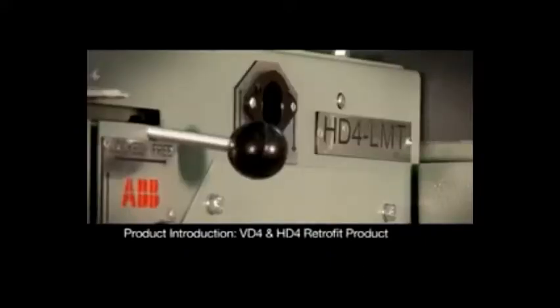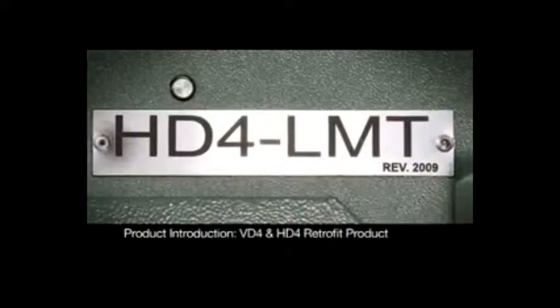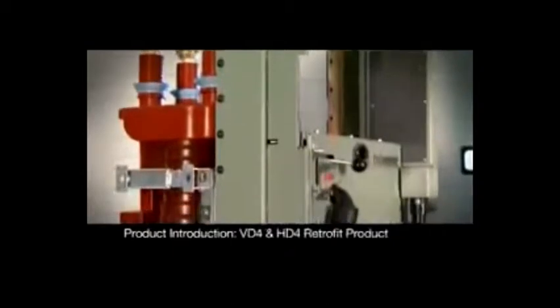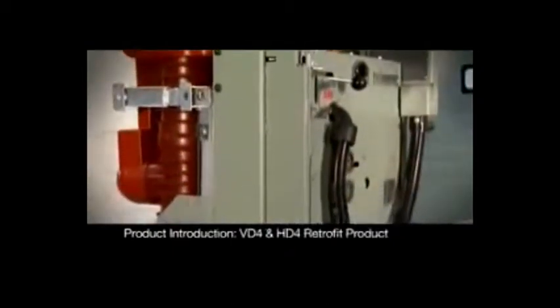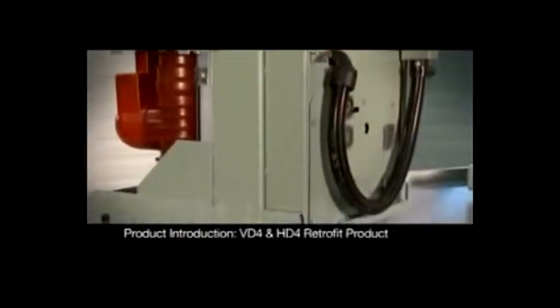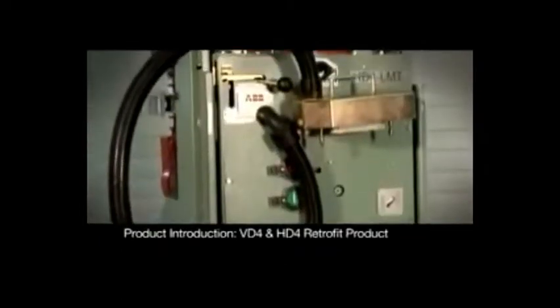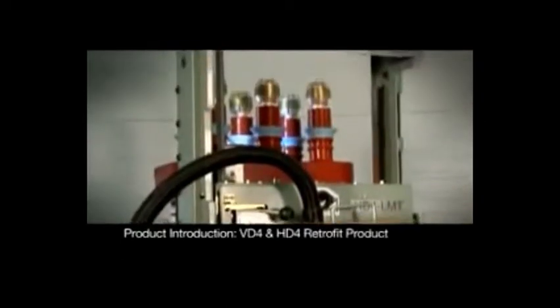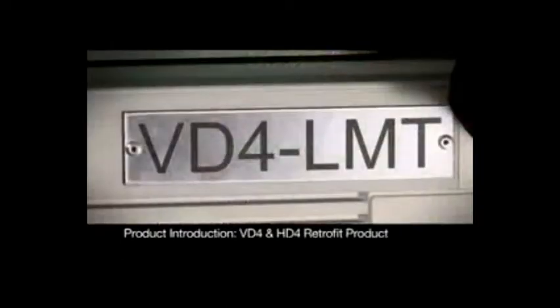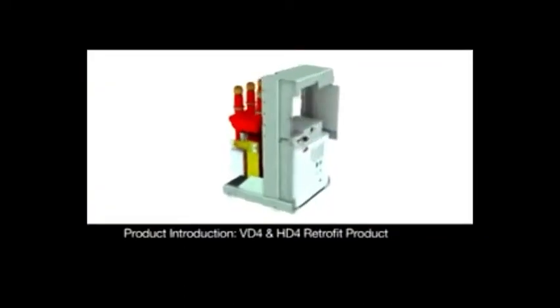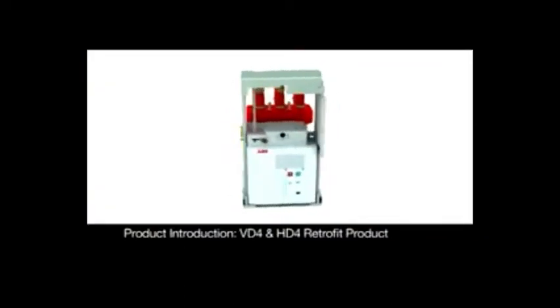The HD4 range has its advantage in that it's a very soft switching, soft interrupting process, which is well suited for capacitive switching and certain specific applications in the market. It's the client's priority and his questioning of what he wants to have installed. So we either offer him the SF6 unit or we offer him the vacuum unit. In the long term, the spares availability is so much easier if you partner with a company that supplies typically 100 to 200,000 of these units globally per year.